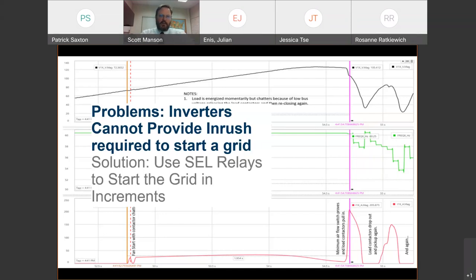This plot is actually an example of an inverter that wasn't picking up load. In fact, it ramped through it. This is our discovery aha moment. This inverter, by the way, one of the best inverters on the market, could not energize even a small fan on a small load bank, a fraction of the power of this inverter. And here you can see the voltage in the top plot went up. And then it collapsed and oscillated. And on the bottom, I think that's frequency and current.